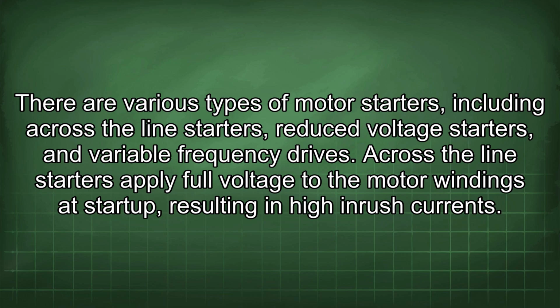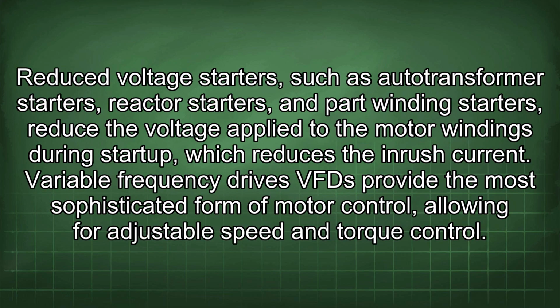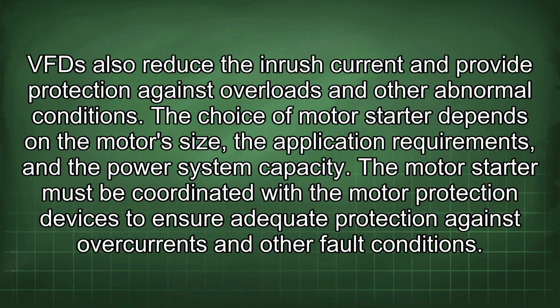Across-the-line starters apply full voltage to the motor windings at startup, resulting in high inrush currents. Reduced voltage starters, such as autotransformer starters, reactor starters, and part winding starters, reduce the voltage applied to the motor windings during startup, which reduces the inrush current. Variable frequency drives (VFD) provide the most sophisticated form of motor control, allowing for adjustable speed and torque control. VFDs also reduce the inrush current and provide protection against overloads and other abnormal conditions. The choice of motor starter depends on the motor's size, the application requirements, and the power system capacity. The motor starter must be coordinated with the motor protection devices to ensure adequate protection against overcurrents and other fault conditions.